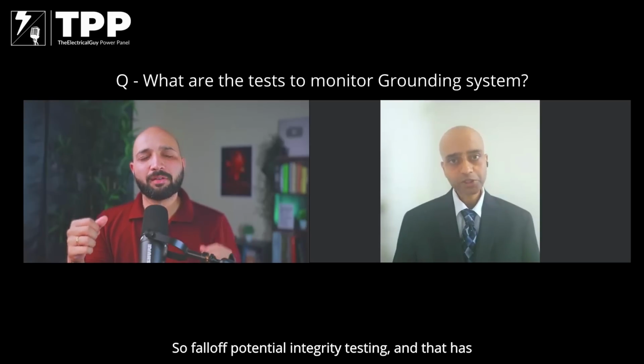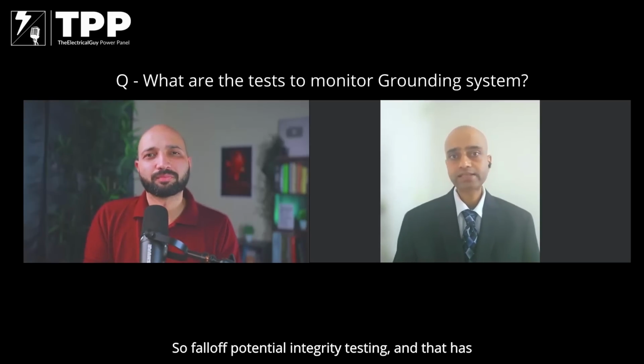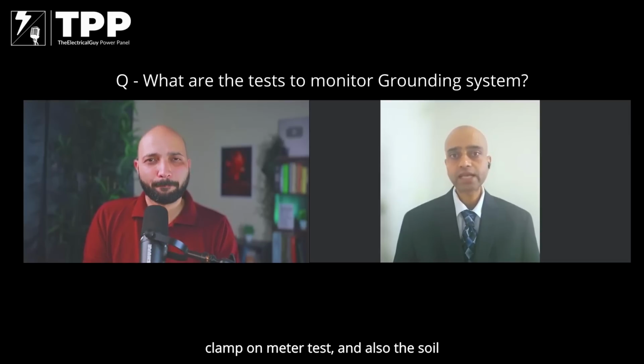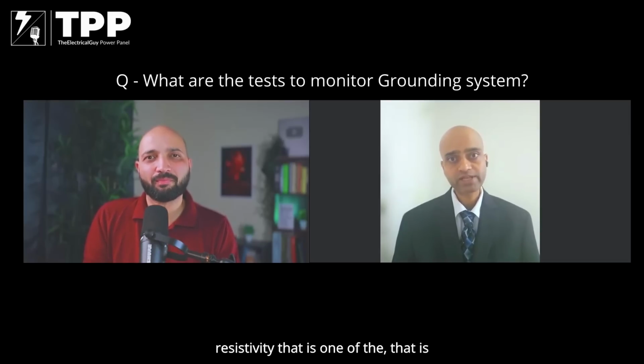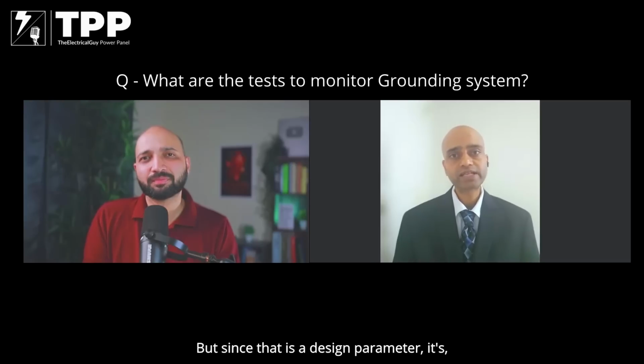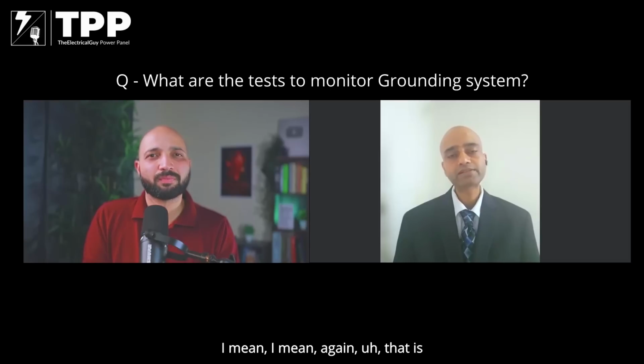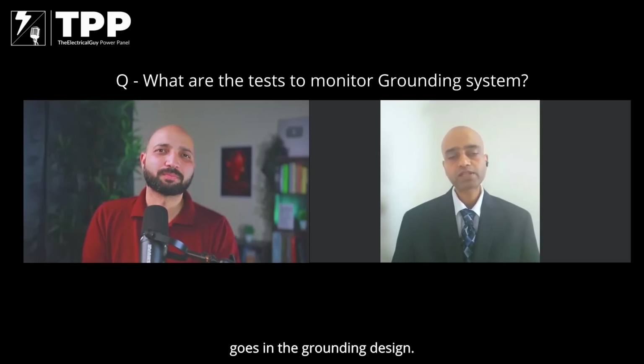Yes, so fall of potential, integrity testing - that has different types of tests, meaning clamp-on meter test, and also soil resistivity. That is one of the tests which is a basis of the grounding design. But since that is a design parameter, again, that is equally important, but it's a first step that goes into the grounding design.